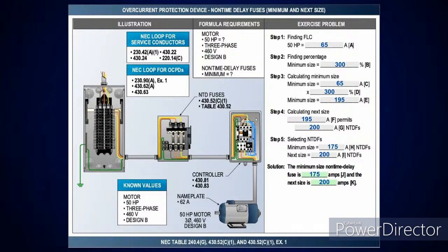All right. Now, the next thing that you're going to get into, and I said make sure you do this last week, I said right there at table 430.248 and 250, write down sizing OCPD, and then put 430.52(C)(1), and then table 430.52(C)(1). Okay, that's where we want to go.